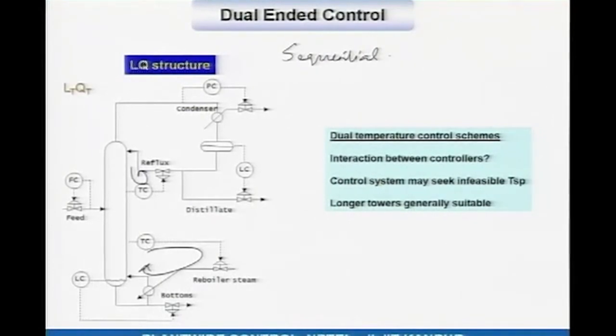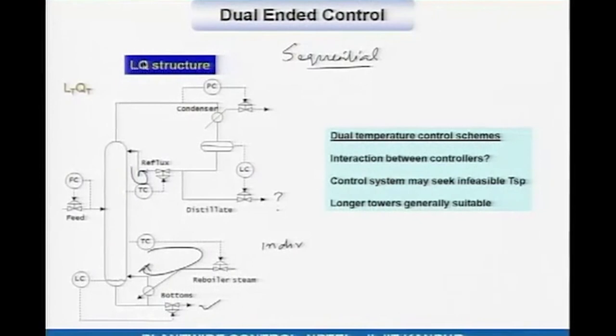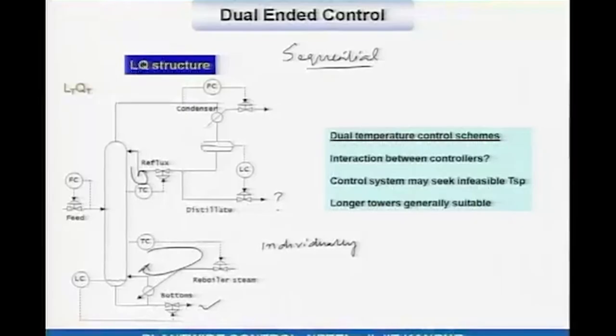Individually tuning is not recommended here. If you tune both loops individually with the other loop off and then take detuning, temperature control here will not be as tight as with sequential tuning. Because the temperature control is not as tight, product purity quality variation would be more, meaning you will have to operate on average at a larger product quality giveaway. So in this particular processing situation the way you tune the loops also becomes important because of interaction.